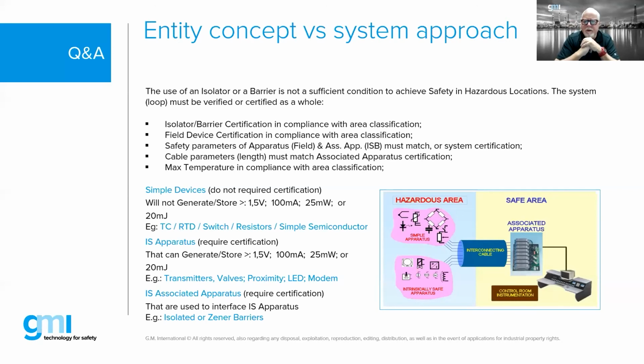One thing to highlight, just to get your head around intrinsic safety for those not as familiar with it: think of it this way. Under normal circumstances, say if we have a 24-volt circuit and a 4 to 20 milliamp signal going between a card and our device in the field, we're never going to have any issues. So the barrier itself will just sit there, not really doing anything. In the case of a Zener barrier, it's basically quiet.